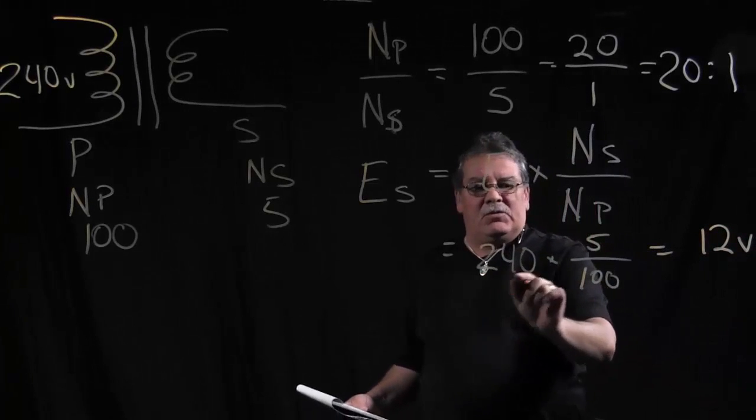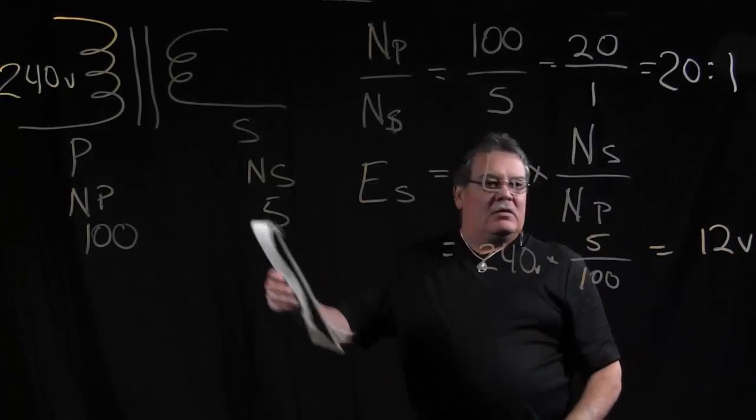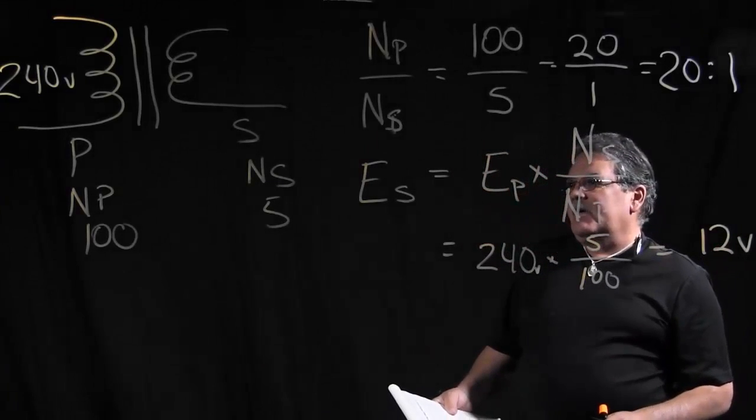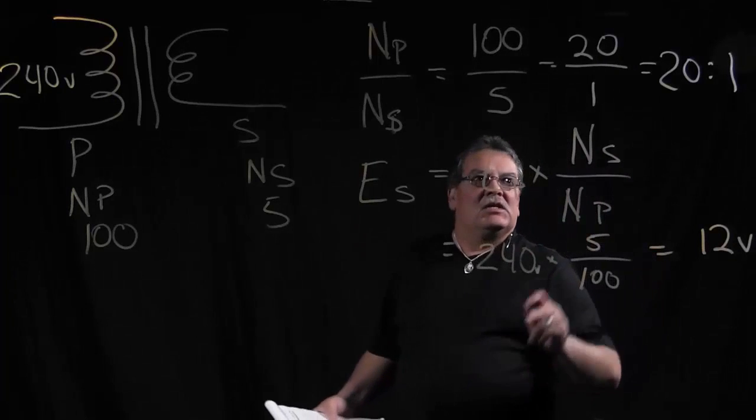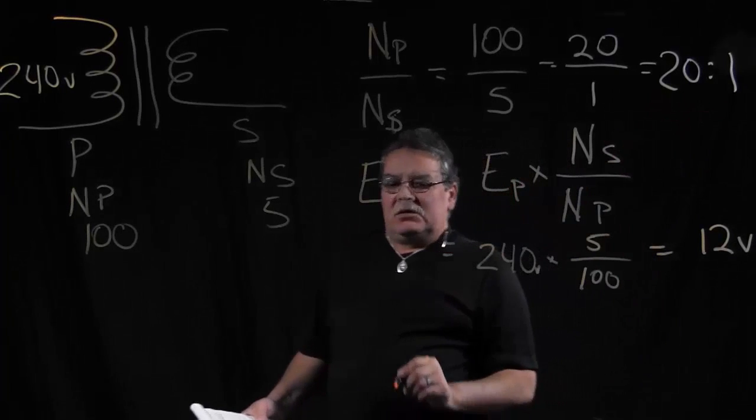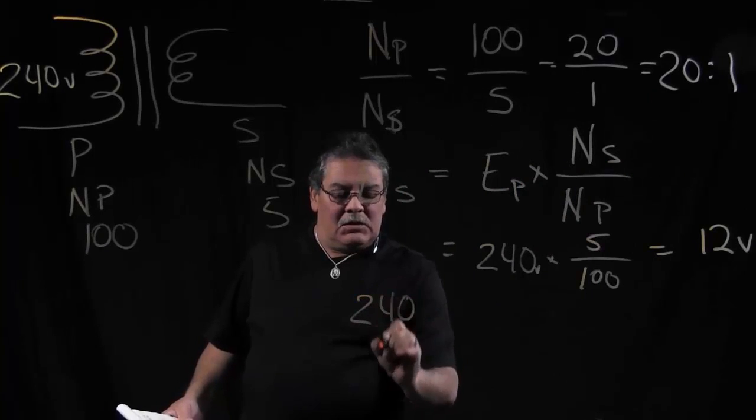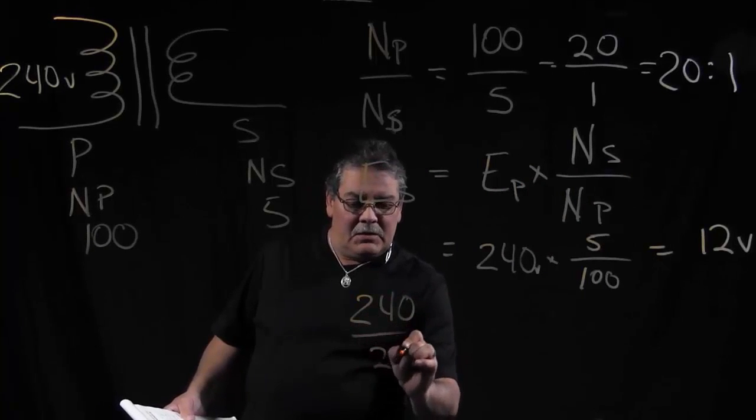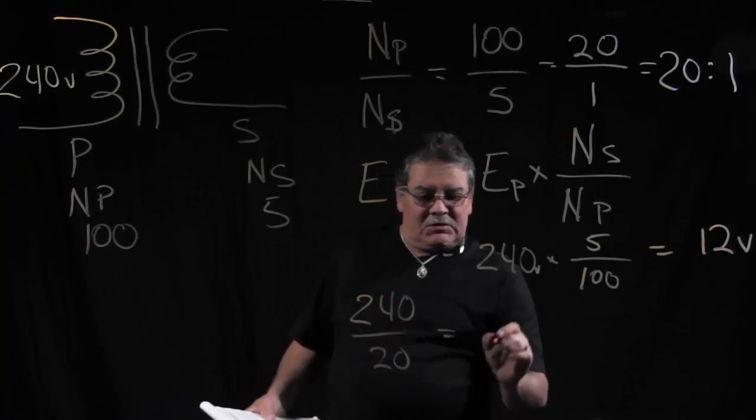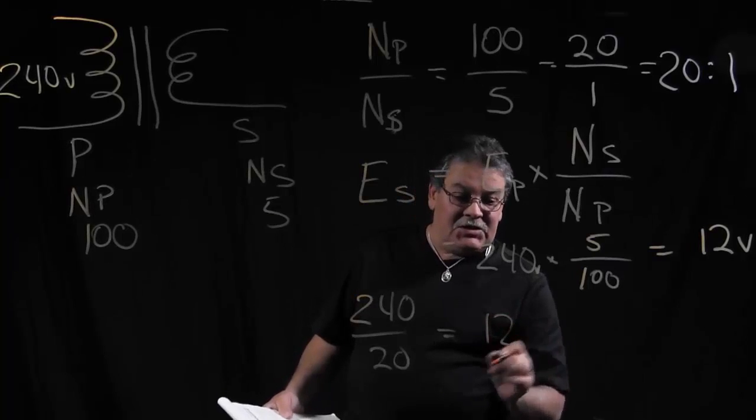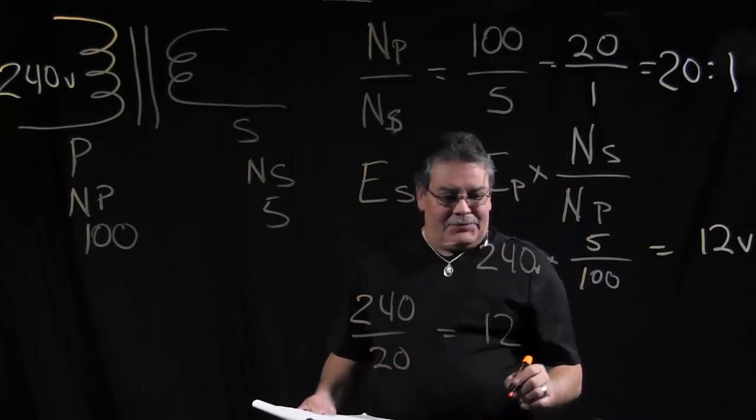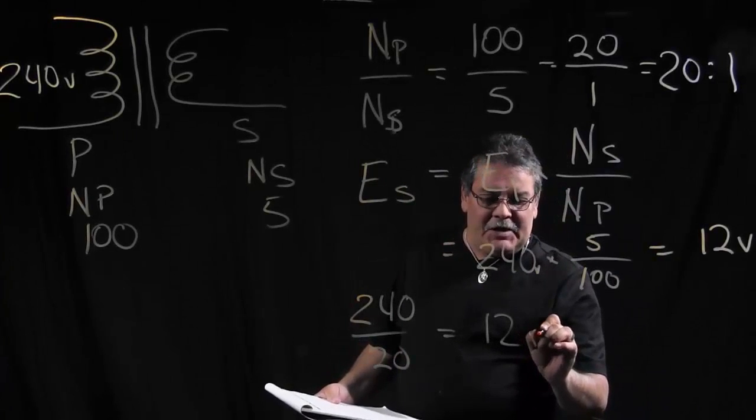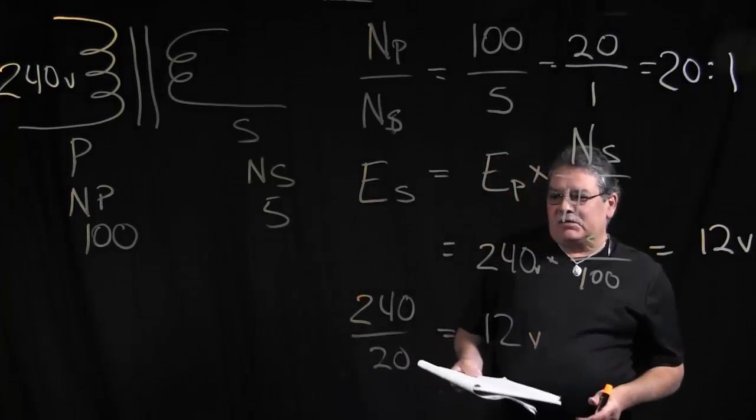So this demonstrates, we started off with 240 volts in the primary, and we have 12 volts in the secondary. A lot of times what I'll do is an easier way: we have a 20 to 1 ratio, so if we have 240 volts divided by 20, it comes out to 12. So that's an easier way to do it than a lot of this other stuff, but that's just one way that I figured out how to do it on my own.